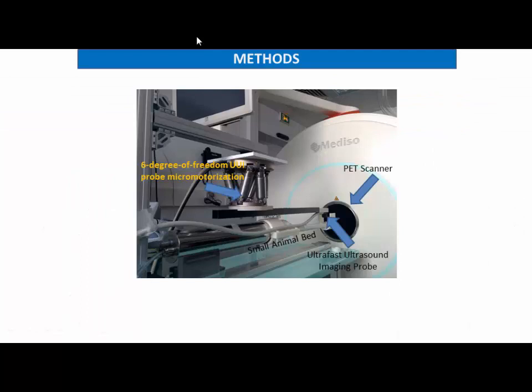So this is what the assembled system looks like. You have here the hexapod that's installed upside down, onto which we install the carbon arm, onto which the ultrasound probe is attached. And you can see that this entire structure is on a moving bed here. So when we move the bed, the hexapod moves with the bed. The bed can be in 3 positions: outside the PET scanner for preparing the animal, it can move inside for the PET scan, and it can move in further for the CT scan.